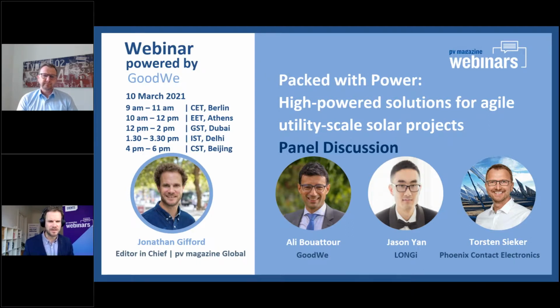What about supplying the C&I space, the commercial rooftop space? Are these requirements for power plant controllers coming in for larger rooftop installations, and will Phoenix Contact supply that? For residential installations, you have feed-in management, but that's done by the inverter itself, which inserts power directly into the low voltage grid (240, 400 volt), controlling power by itself. But for a large commercial rooftop system with a central transformer and substation, you need an additional power control unit to control the power at the grid connection point. That's the topic behind it.